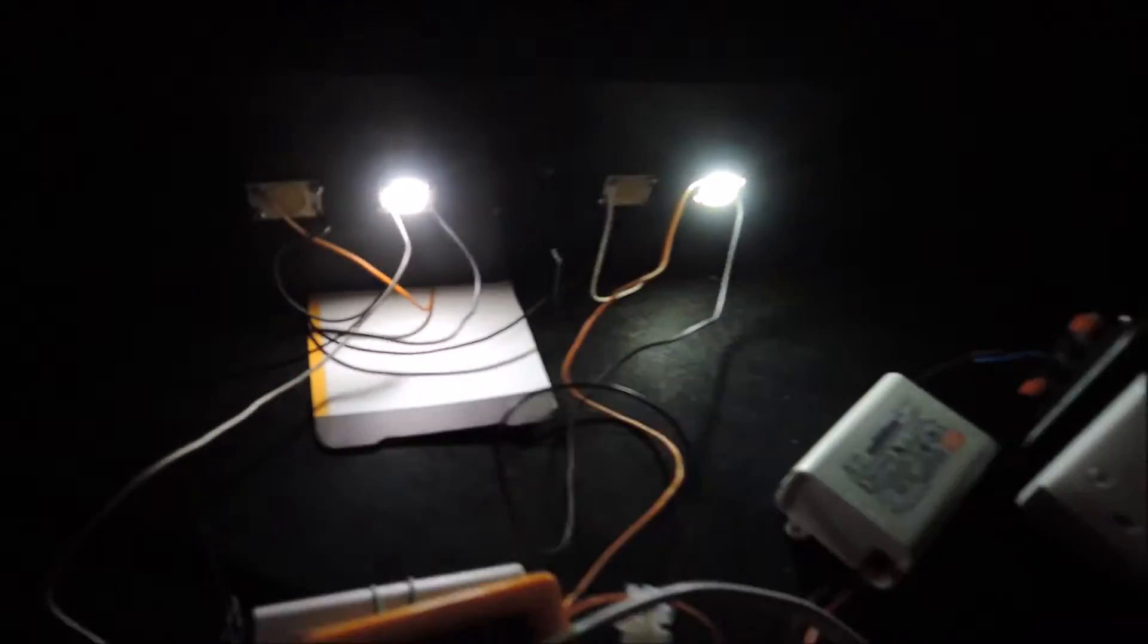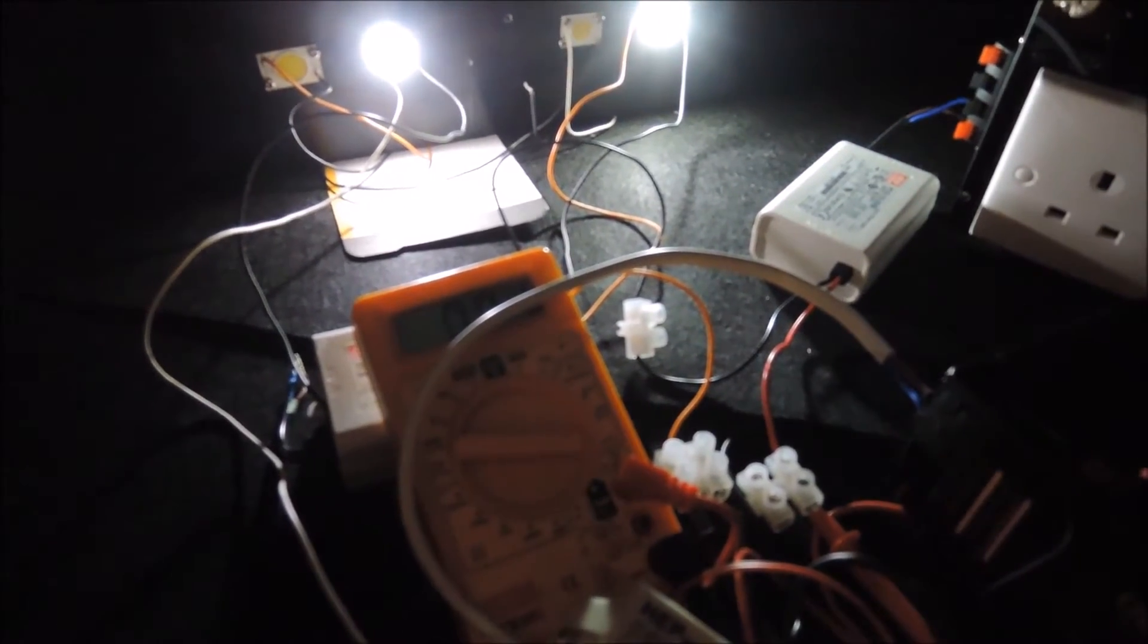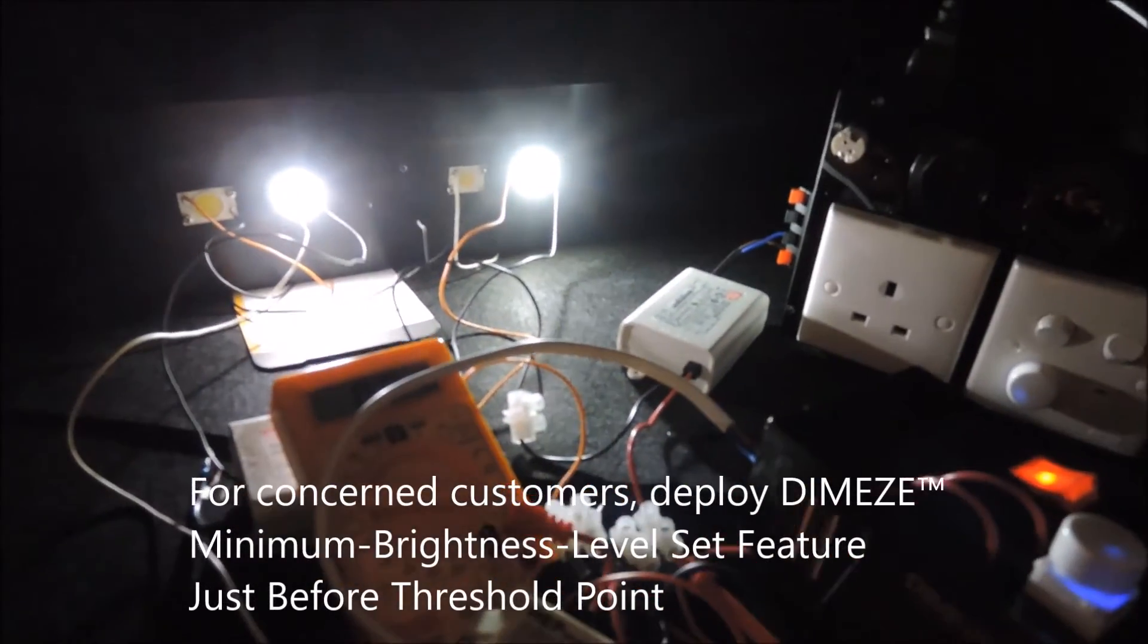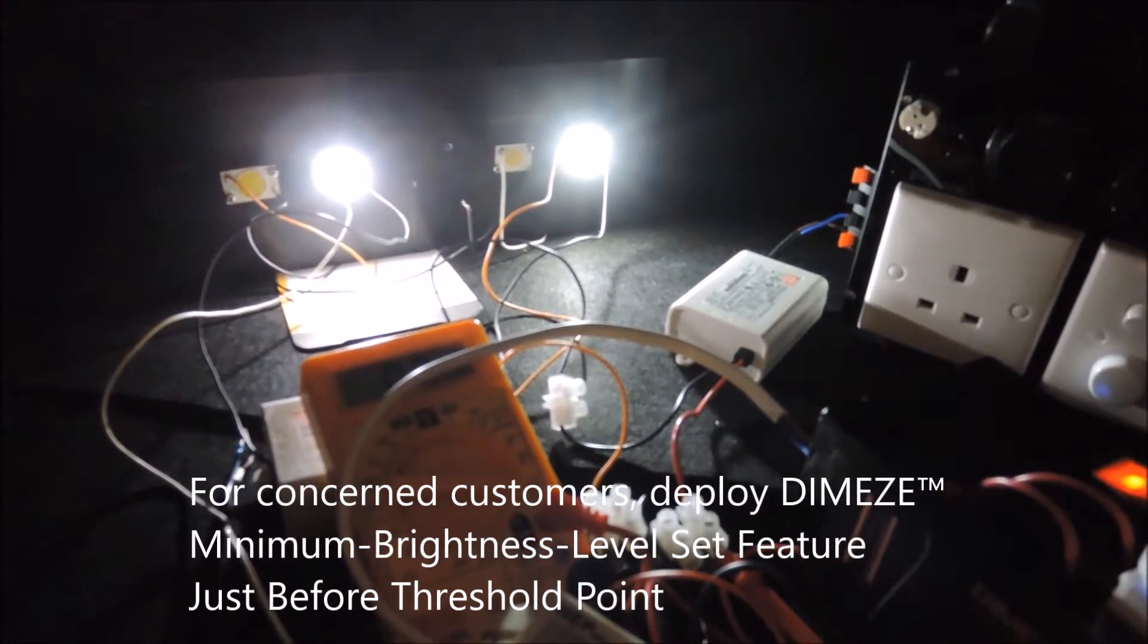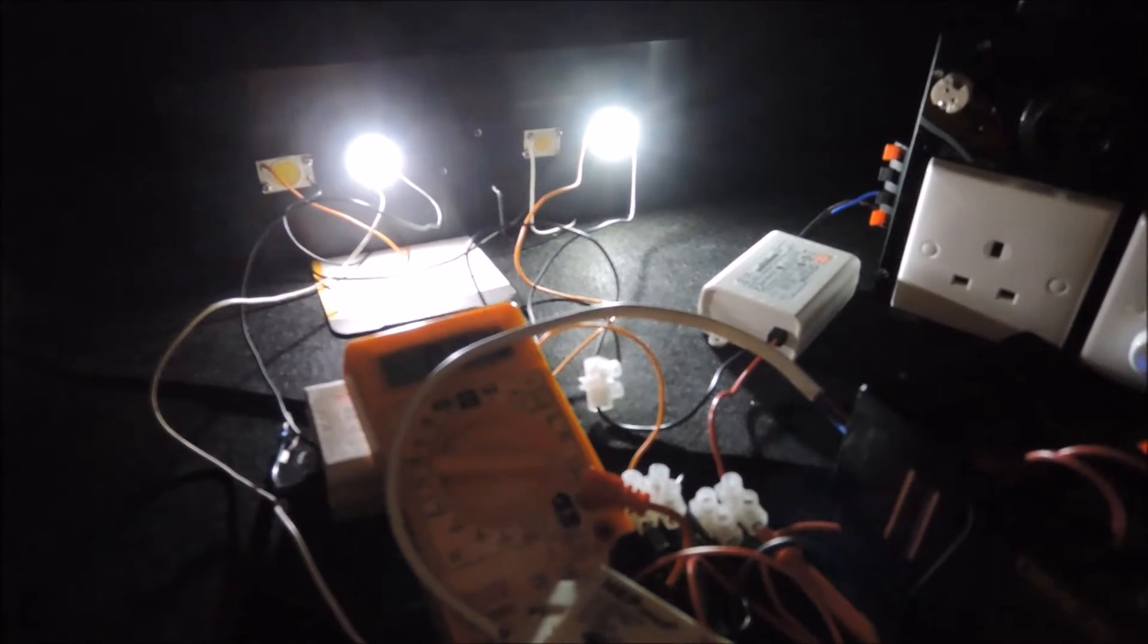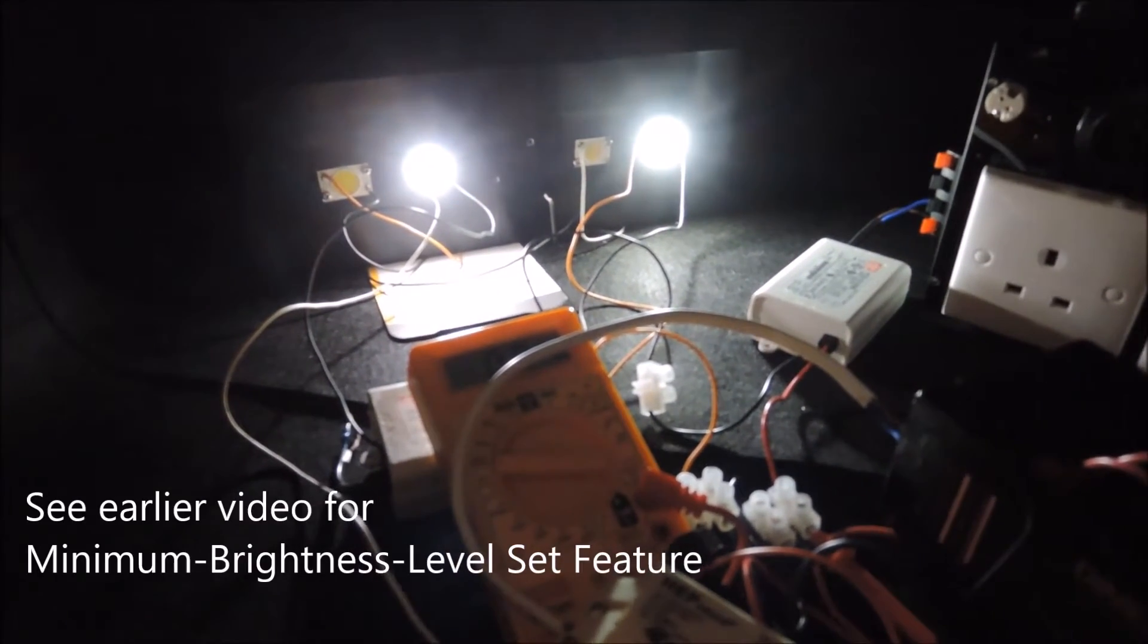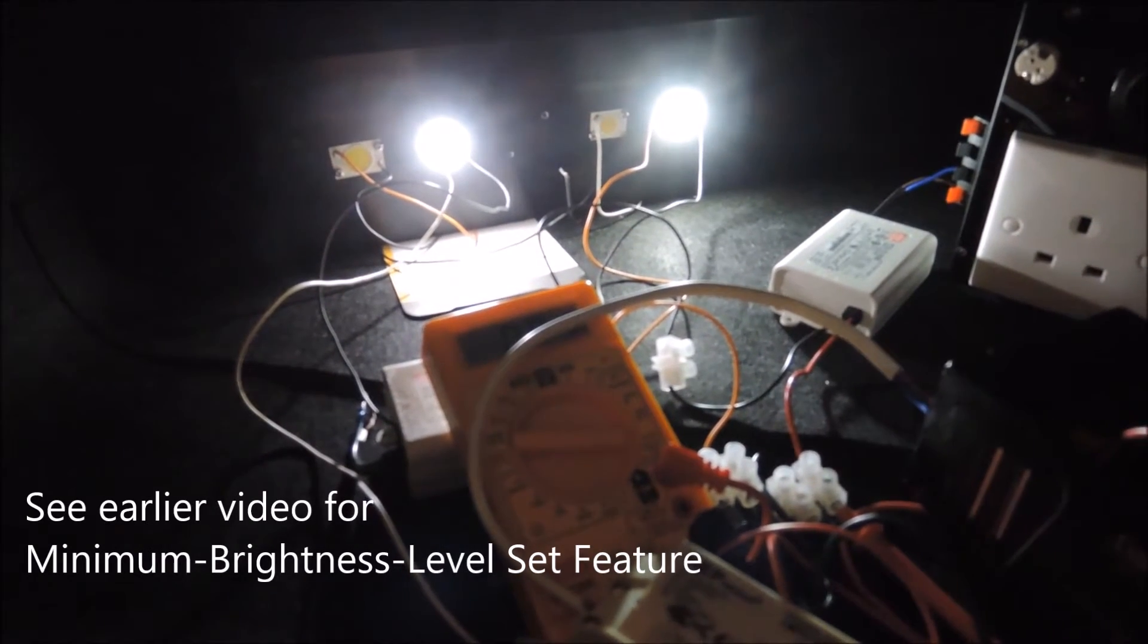So you can see the light output is not as stable as the other. Now if that's a concern in the application, we would suggest to use our minimum brightness level feature to set the brightness level above the flicker point with the HEP driver to avoid undesired effect. Please check our other earlier video for this feature setting.